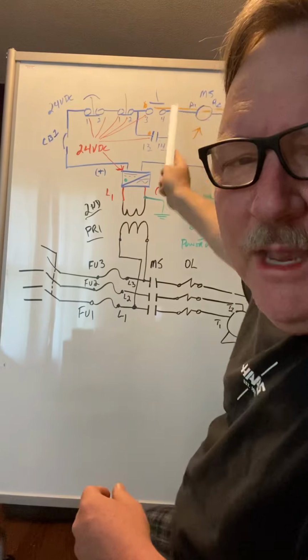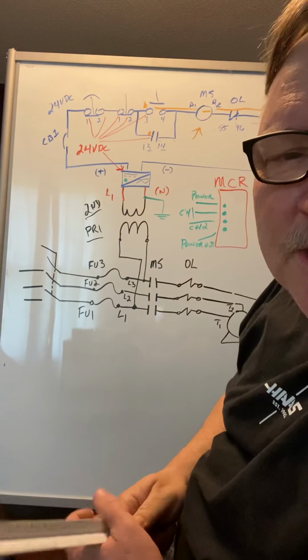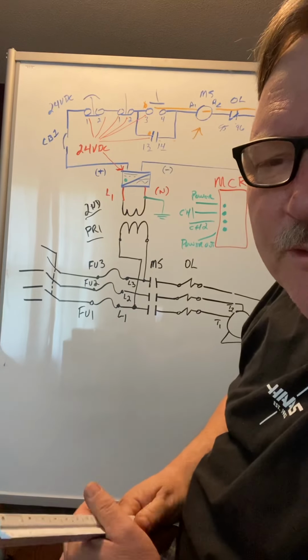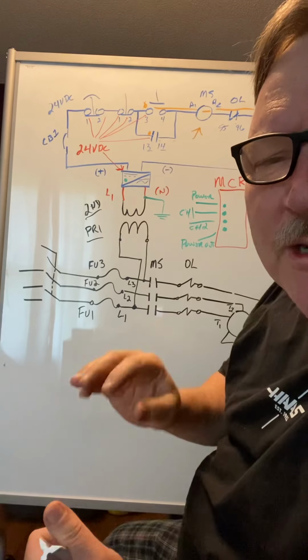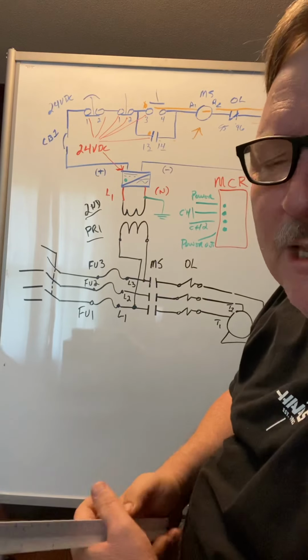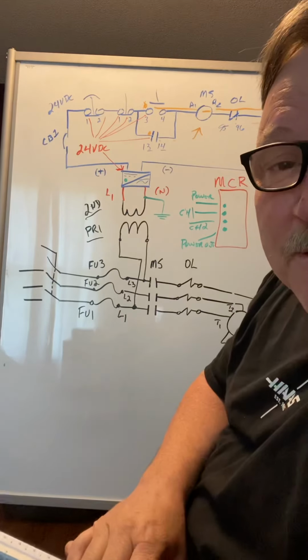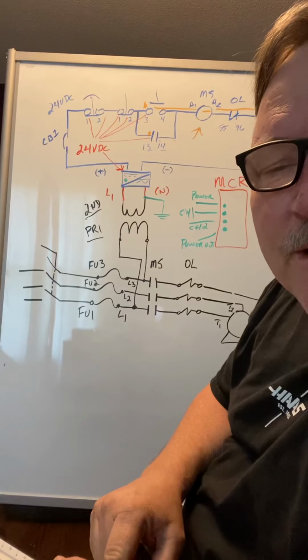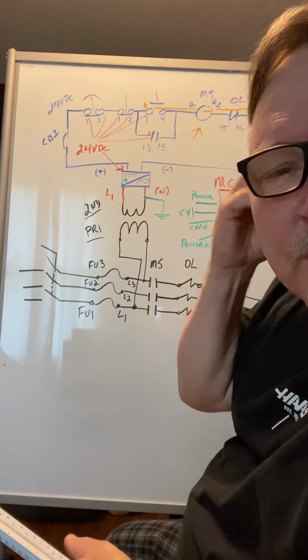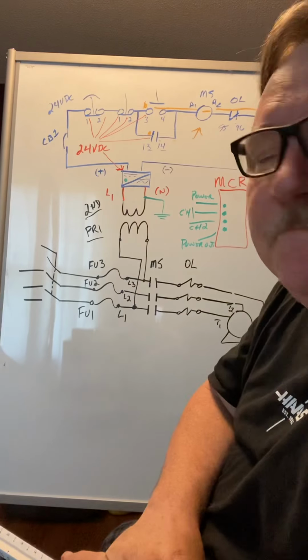That's the basic on a push button switch that your machine doesn't go on, but you can manually push it in. And when you do manually push those contactors in, please use an insulated screwdriver. Don't use your finger. Those things will blow up on occasion. You get a little bit of metal dust depending on the manufacturing process. They can just act up, and your Mr. Squiggy there will look like a hot dog that's been overcooked and just burned open, okay?